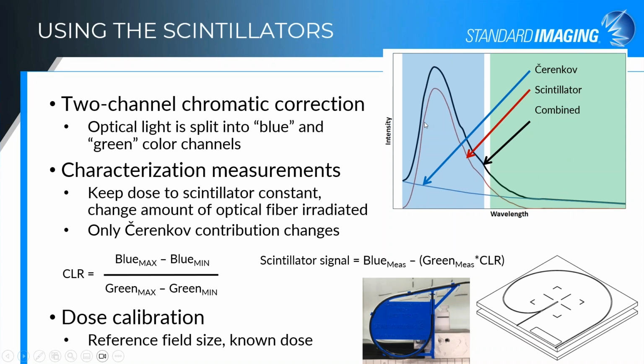Our scintillator is a blue region scintillator. So most of what is captured within that blue range is scintillation signal. There is some Cherenkov that's included in that because the Cherenkov is a broad spectrum contaminant. The green portion of the signal is primarily Cherenkov, but there's a little bit of that scintillation tail that crosses over into the green region.